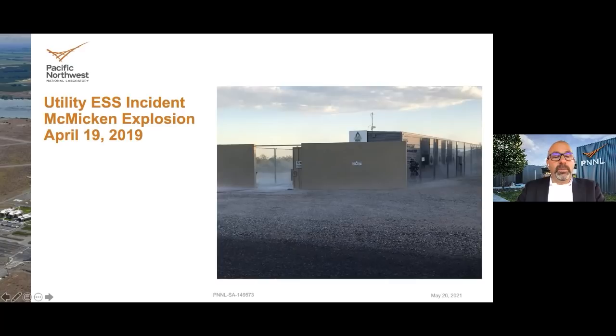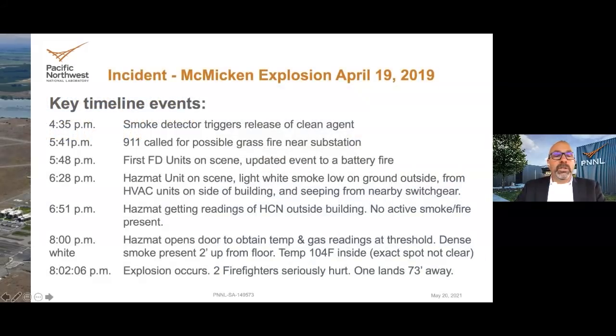I'll show you a timeline of what occurred. At 4:30 in the afternoon the smoke detector triggered on a fire in one of the battery racks and released the clean agent, but as I said, there was a delay in notifying the fire department. It was over an hour later that somebody called 911, our emergency number. The fire department showed up about 7 minutes after that.